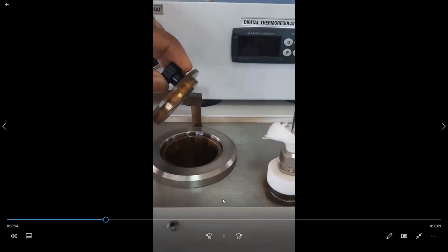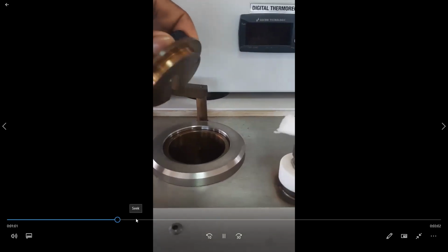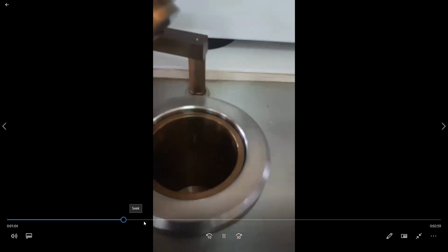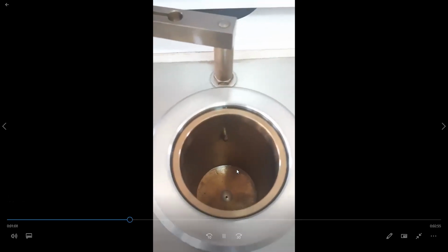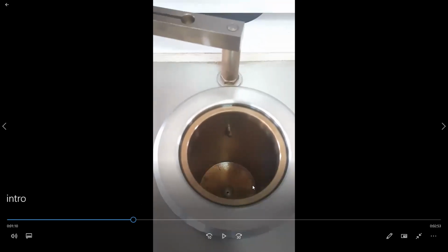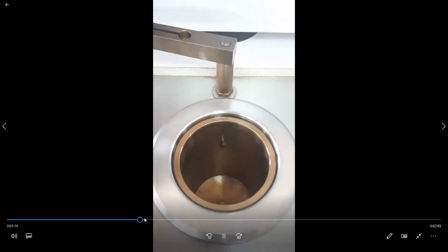There are two cups, so simultaneously we can derive viscosity for two samples. You can see in this cup there is an orifice, a small hole, and this hole has a spherical shape, and after that there is a small hole down there. Inside this cup, the orifice is in the middle of the water bath.